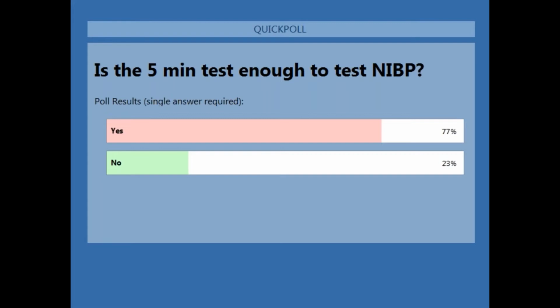Now, my opinion and my experience is that it wouldn't add a whole lot more time. So maybe it takes longer than 5 minutes to determine a full patient monitor performance test. When I add in these extra tests for NIBP, it's still not going to be more than 10, certainly not more than 15 minutes. Now, why am I worried about how much time it takes? Look, y'all have way more to do just in testing alone than you have time to get around to for everything. I know how it is because I've carried the bag. I've done what you do.